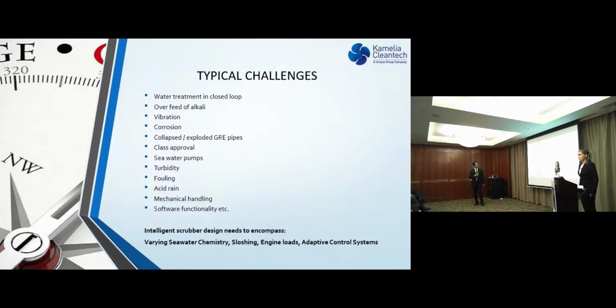Mechanical handling: what happens most of the time is you look at if the system fits, okay, everything is done perfectly, but can you actually take everything out that you need to take out? Can you operate it as per requirement? And software functionality, that can be challenging with chemical controls for closed loop. Most mechanical engineers are not aware of chemistry enough to actually design a system. Very true. Yeah. And well, basically, if you want to make an intelligent scrubber system, you have to encompass these things. So you need to understand seawater chemistry in general, sloshing, engine loads, and you need to have adaptive control loops.